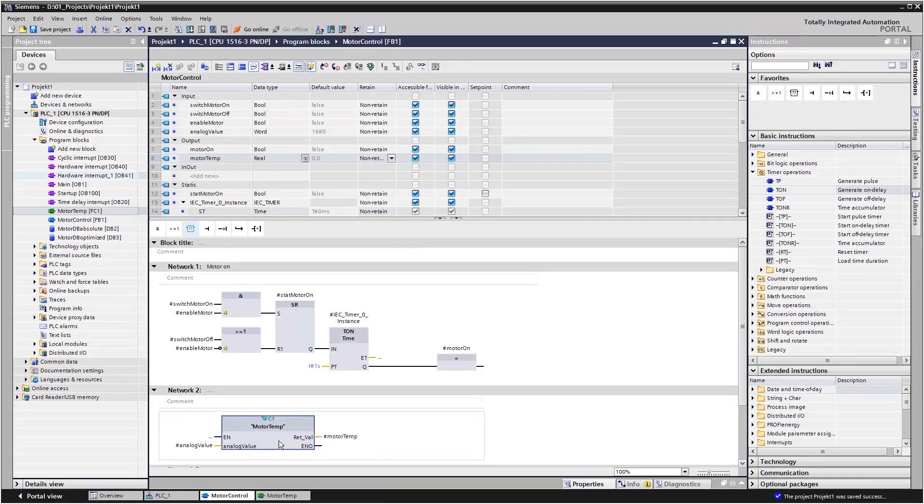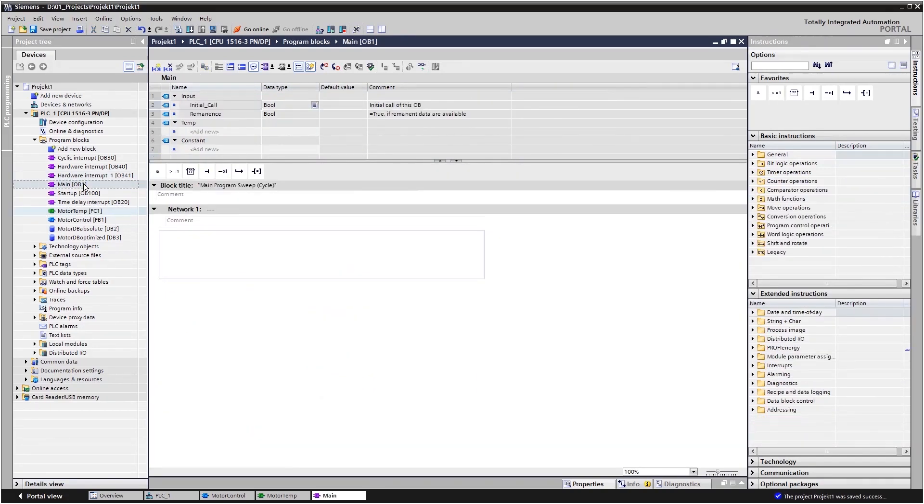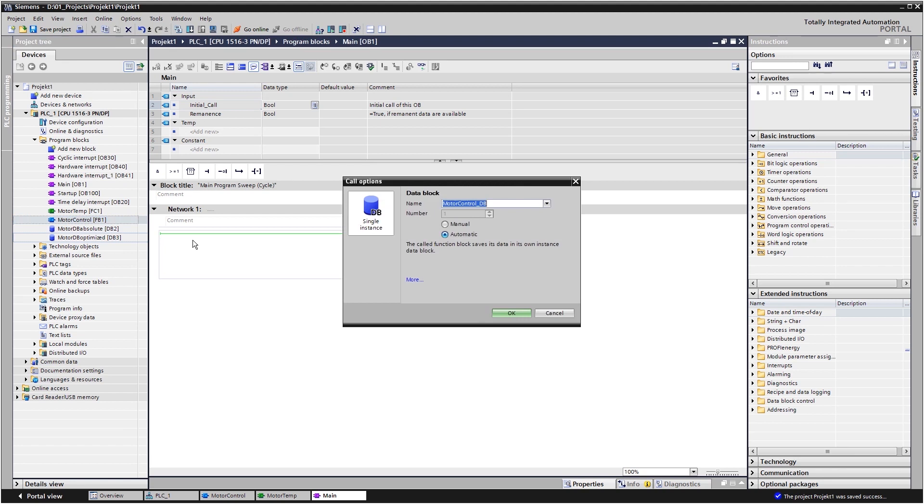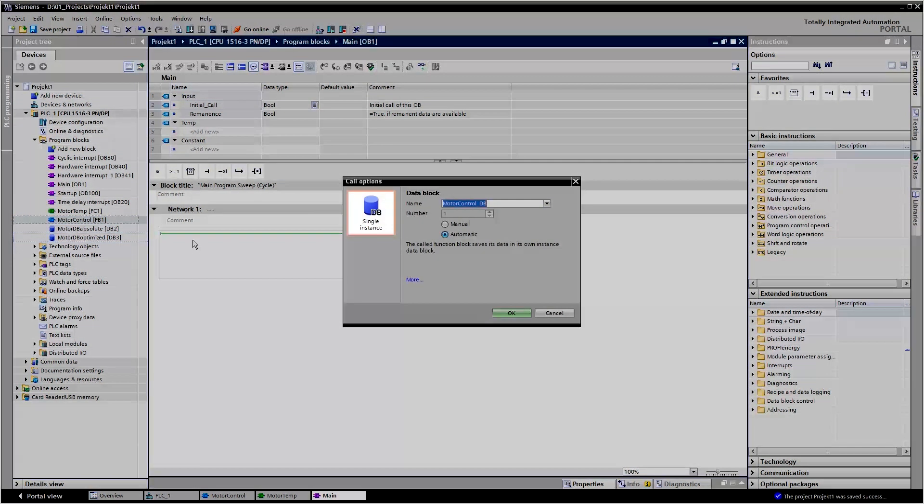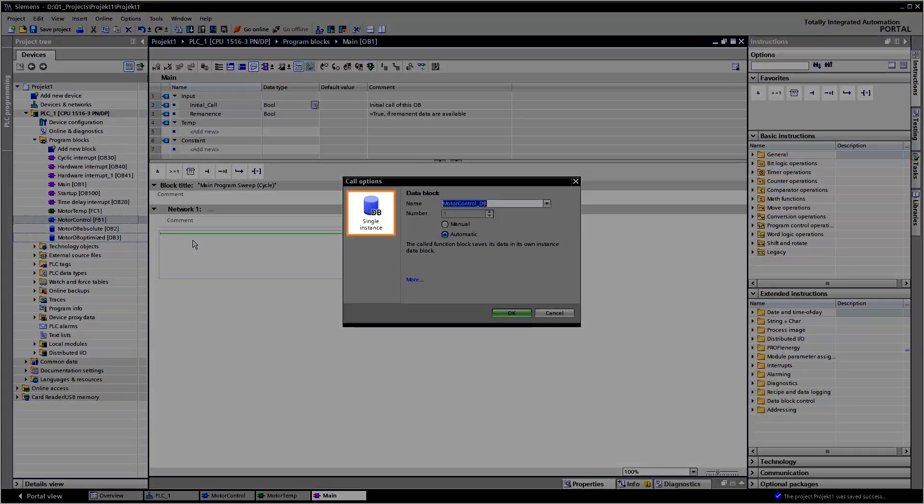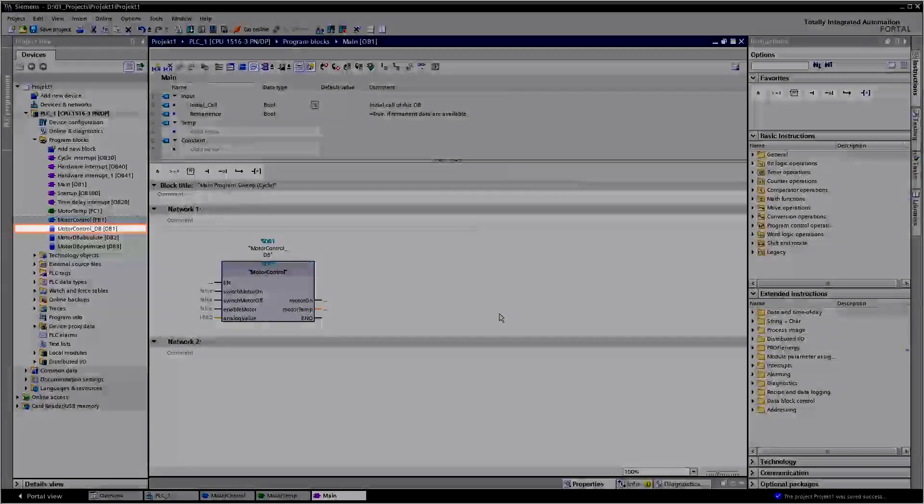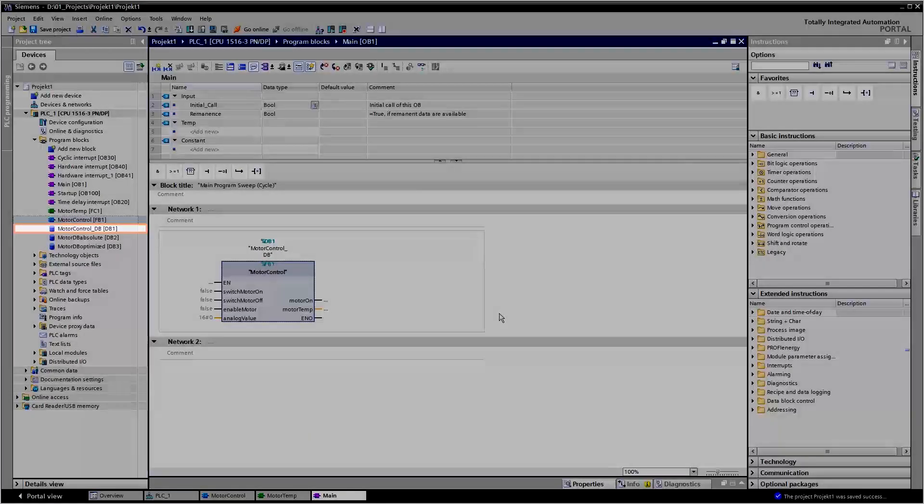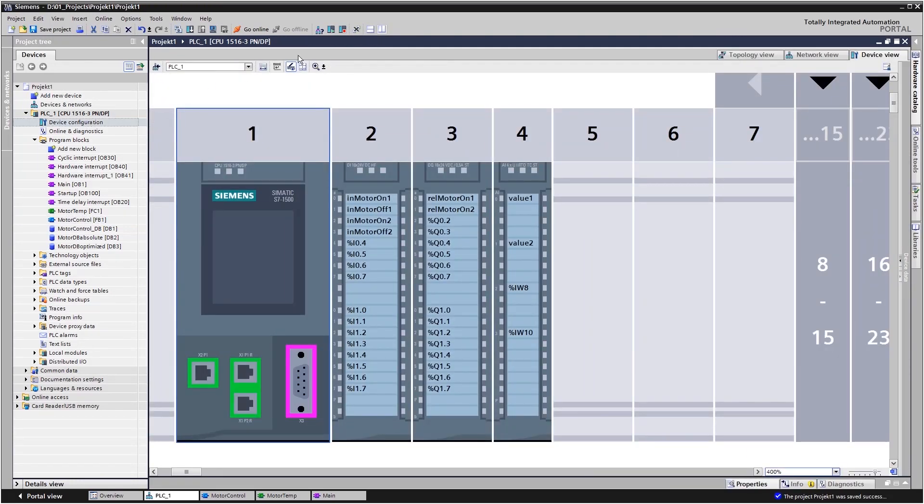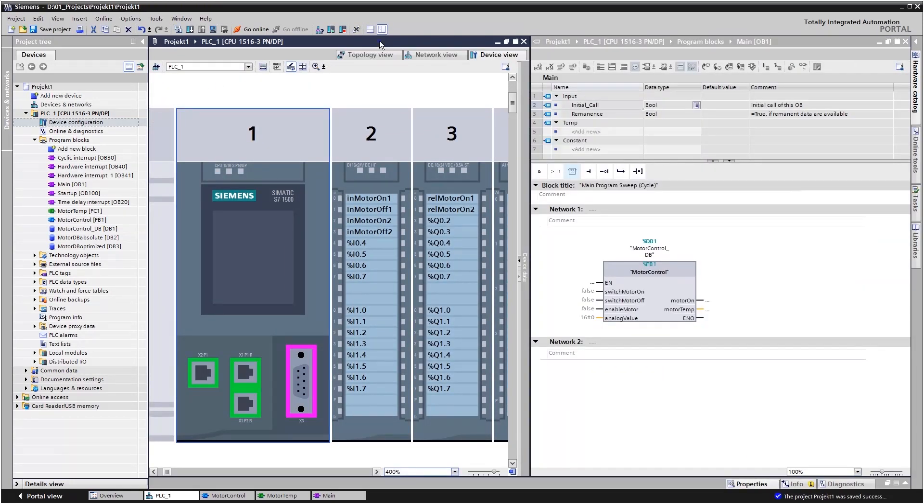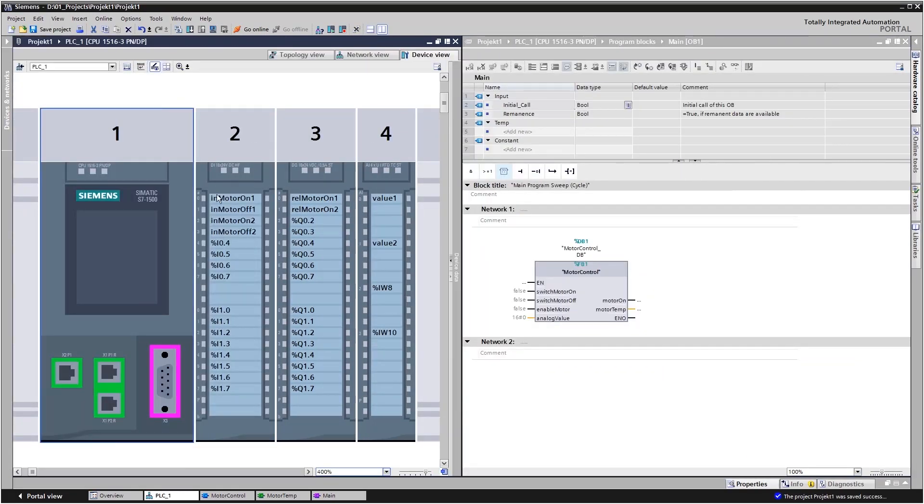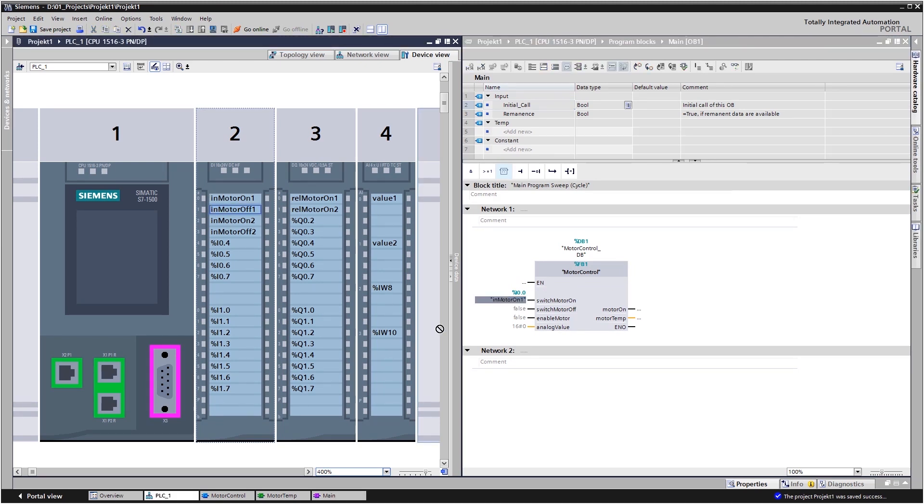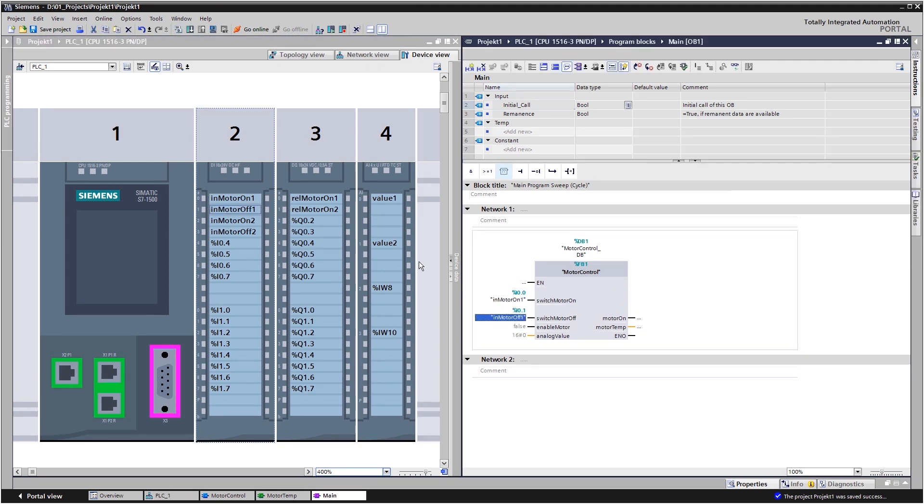The function block programming is now complete and can be called up any number of times. Calls from within an OB are available only with single instances. That is why with each call up an instance block is automatically created, and the block parameters are connected to the hardware inputs and outputs.